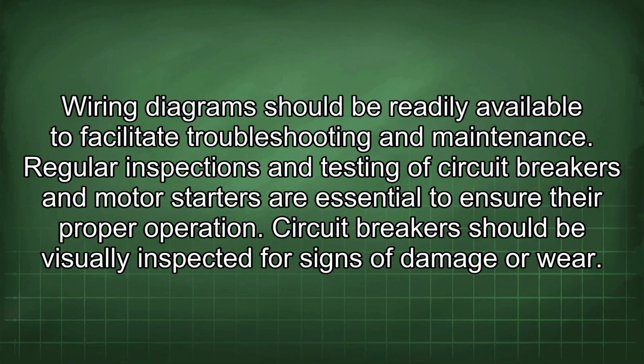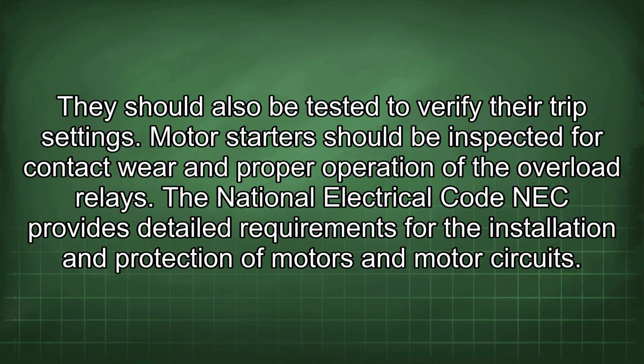Regular inspections and testing of circuit breakers and motor starters are essential to ensure their proper operation. Circuit breakers should be visually inspected for signs of damage or wear. They should also be tested to verify their trip settings. Motor starters should be inspected for contact wear and proper operation of the overload relays.